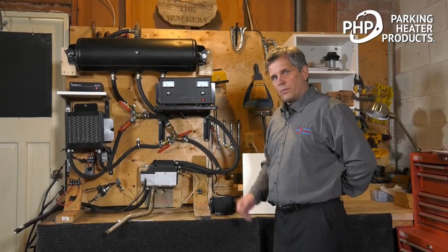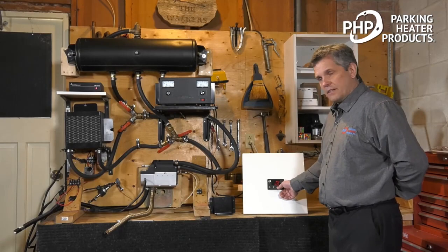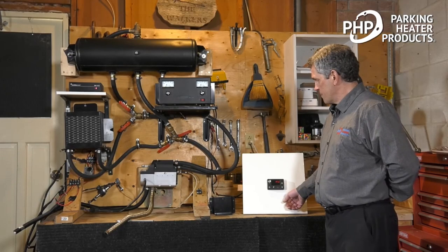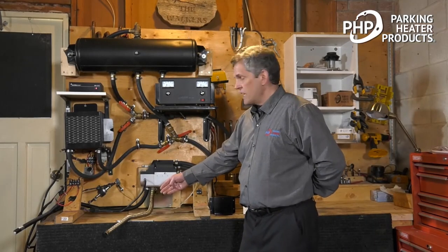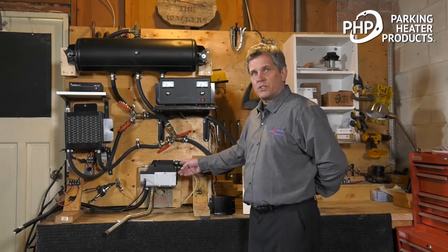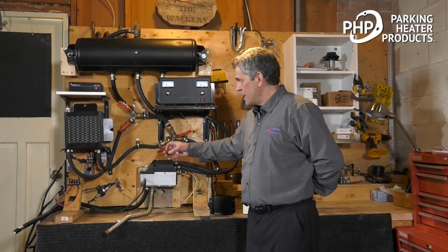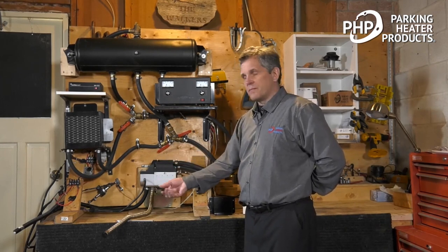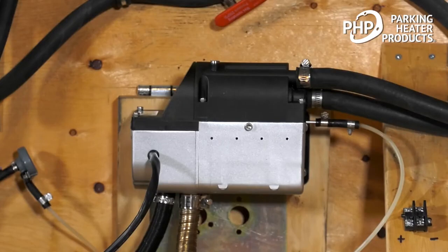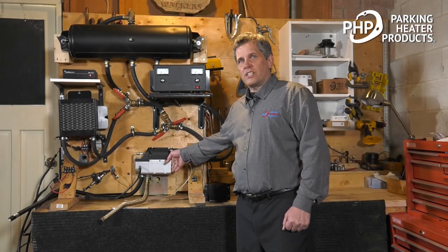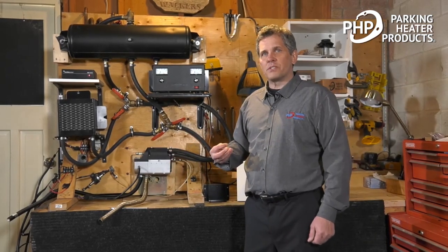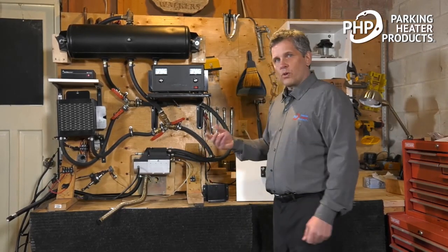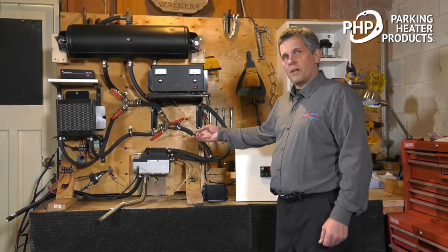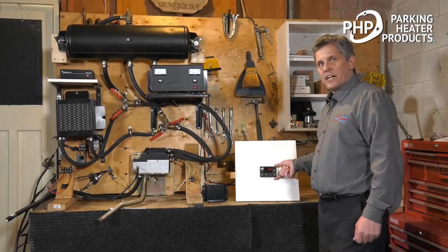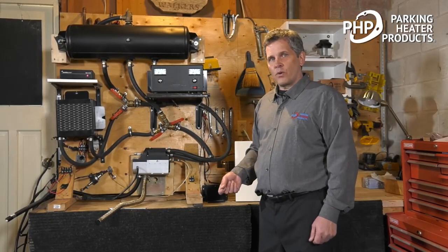To switch the heater off, we simply press the heat button. The fuel pump stops pulsing and the flame is extinguished. Now the blower motor and the water pump will continue to run for a 3-minute cool down that allows any unburnt fuel to pass through the system. Whether you're using our 5 kilowatt Gen 1 engine heater or other engine heaters, the operating principles are basically the same. To find out more about the installation, operation, repair of the heater or the operation of the timer, consult our video library or our manual.